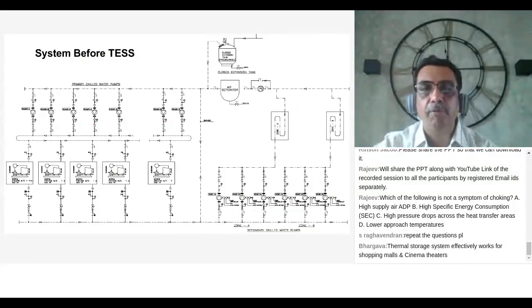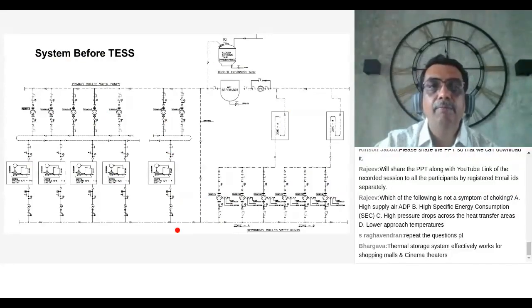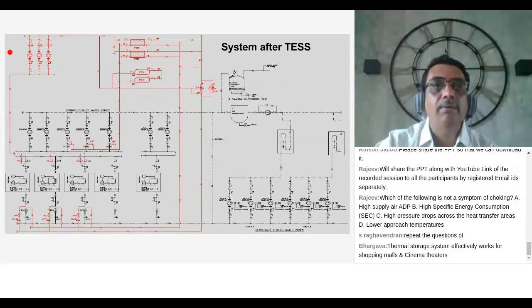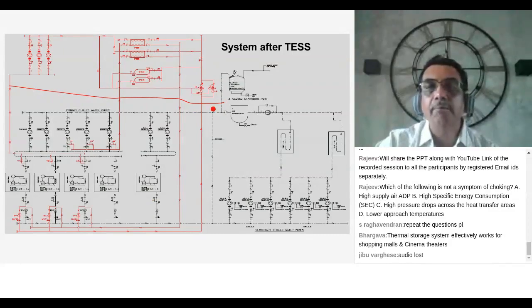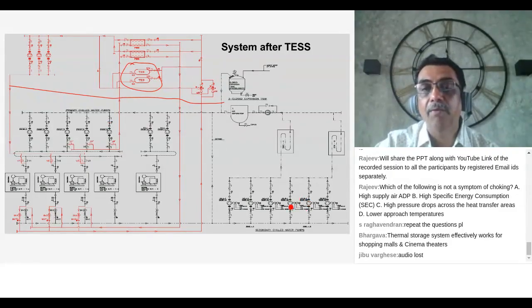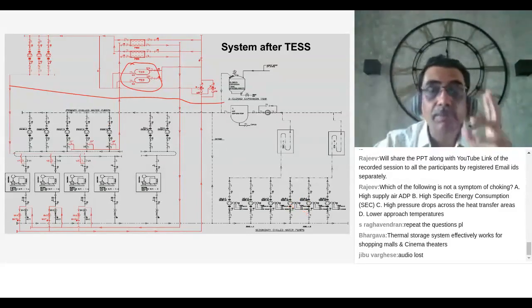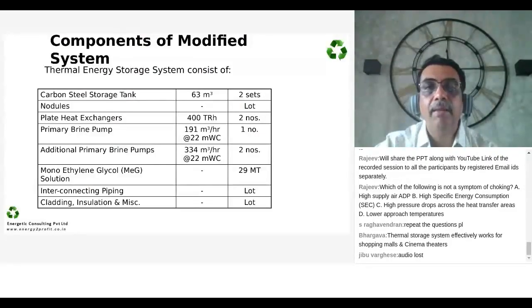This was the system before, and you could see in this entire system, okay, not much addition, only this pumping, this portion got added. Very minor change. These were the storage tanks that got added. So minor change, some PHEs, some tanks and some pumps. Mind you, we are talking about 4100 TR-hour, that is like a 500 TR continuous operating system, not a small system. What were the components? So this was the storage tank, 2 sets of these were the nodules, these were 400 TR, 2 number PHEs, primary. These were what got added.